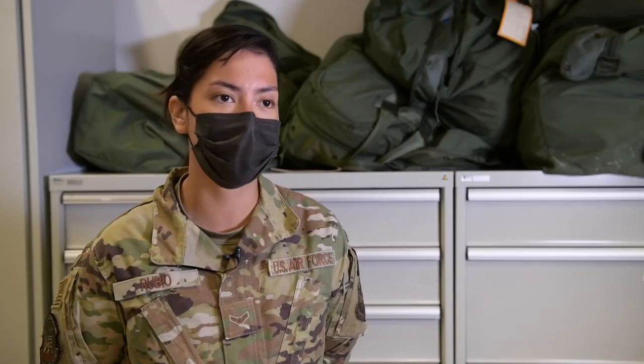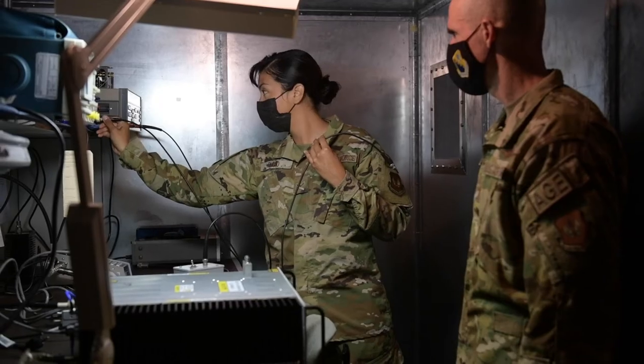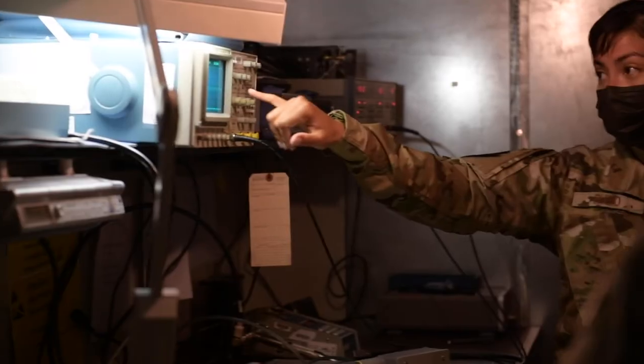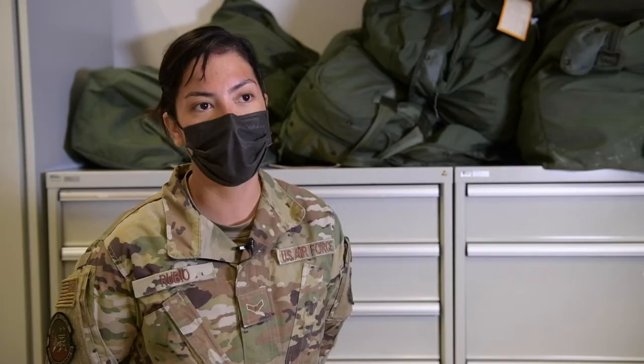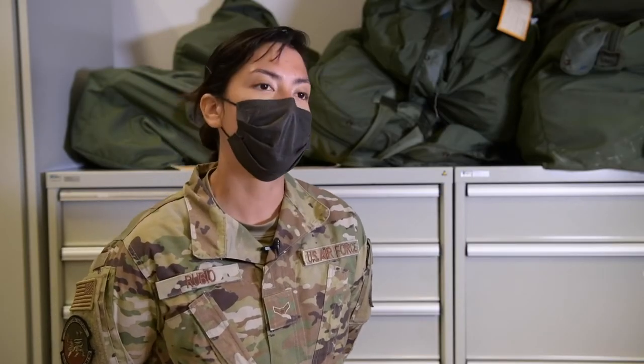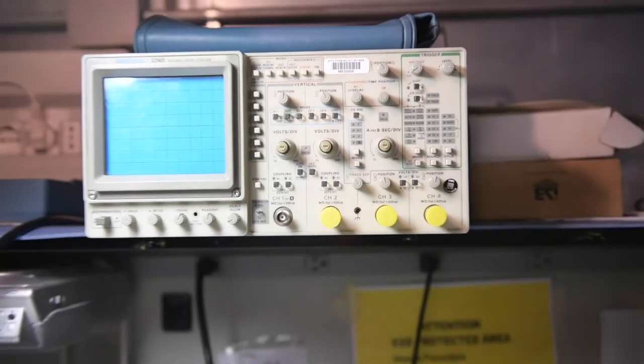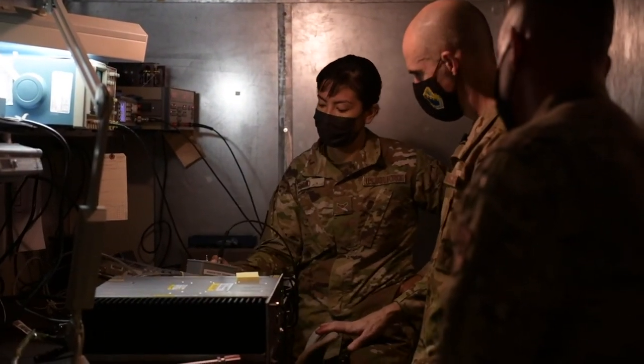The same applies for the receiver. The transmitter test assembly is basically a box that you use to key the radio and then input audio into the system. The o-scope will display an image of the modulation for the transmitter. Once you're mixing your audio and signal together in a small mixer, that will display on screen where you check the modulation. The audio analyzer inputs noise, imitating a person speaking into the radio, and the signal generator is what's actually sending RF through the radio for them to mix — giving you audio and an image.